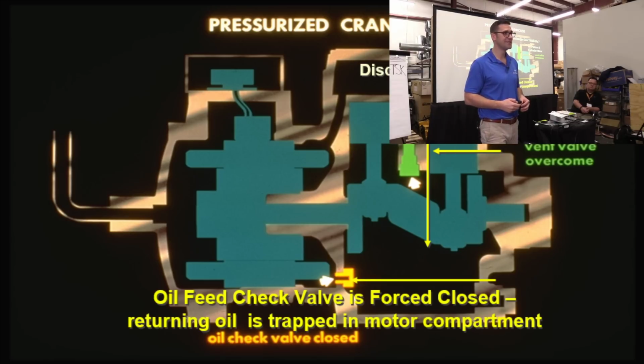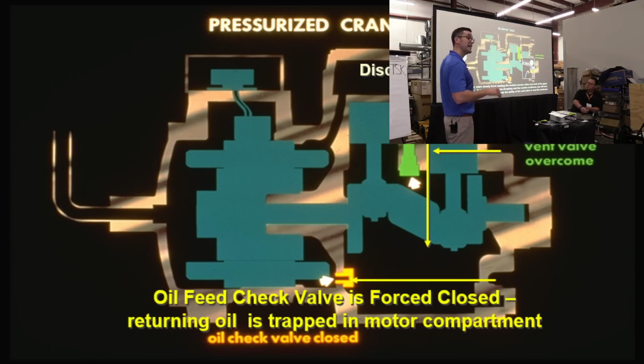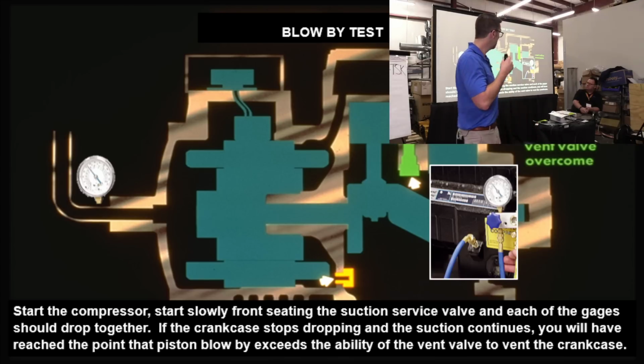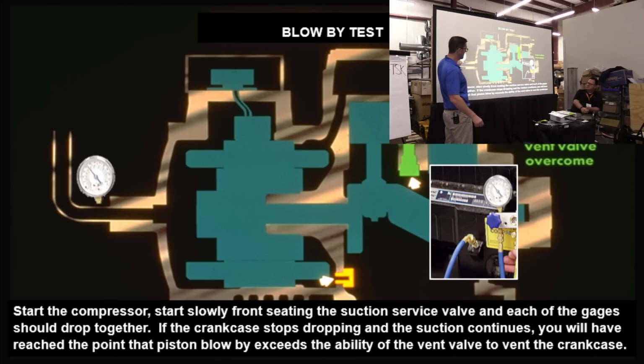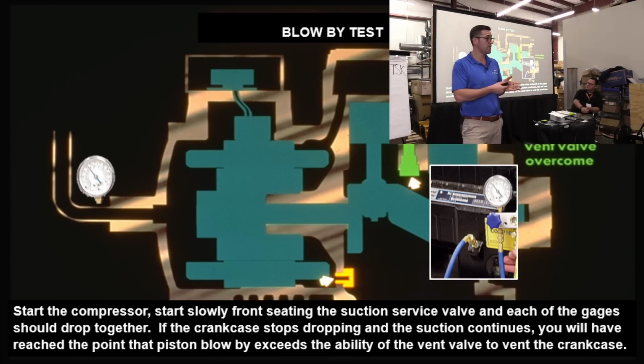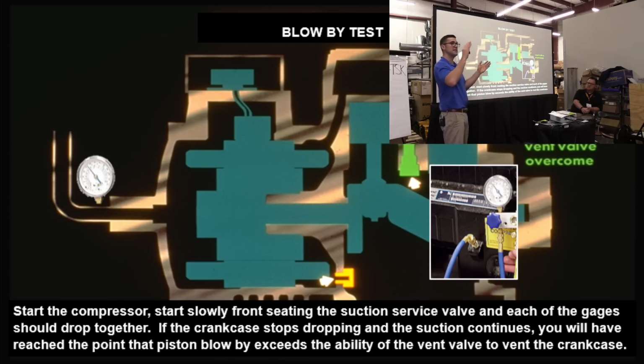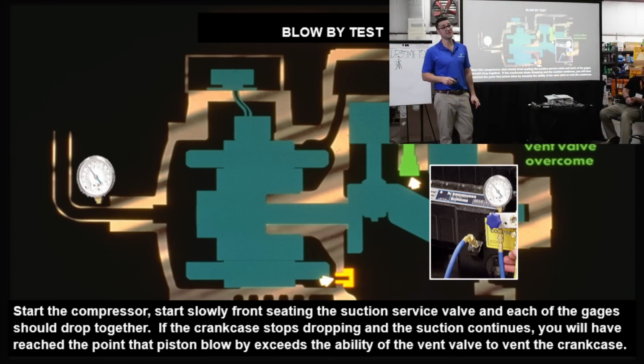Okay. So how do you check for blow-by? Does anybody know? You'd say compression test. So I'm going to give you a tip right here, and I didn't know how to do this before I started working at Copeland. When you're checking oil pump pressure, you should always be doing it on the crank. Most of the guys, and I've always done it on the suction. But you have to remember, it's always 2 psi higher. So when you're doing it on the crank, you put a low pressure gauge there, a low pressure gauge here. You slowly shut the suction service valve, and you watch the gauges. Gauges drop, drop. If this valve is overcome from blow-by or discharge gas, as it says here, this will stop dropping. What do you have to do with the compressor now? Replace it.